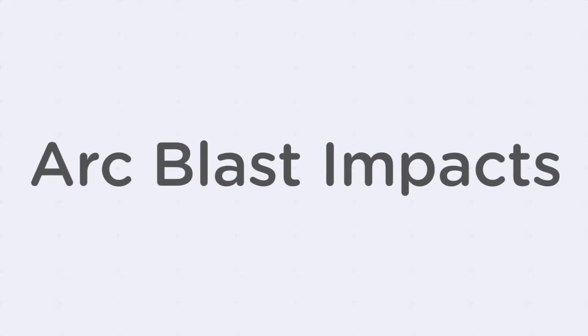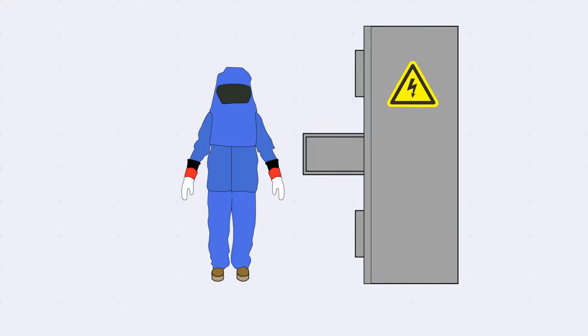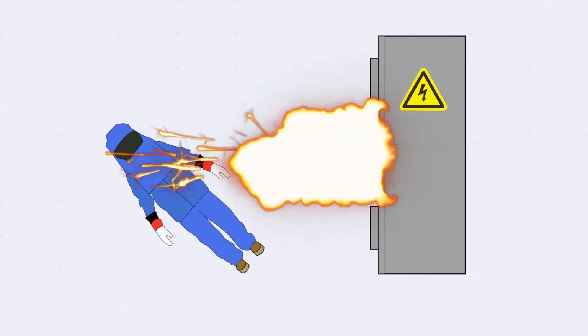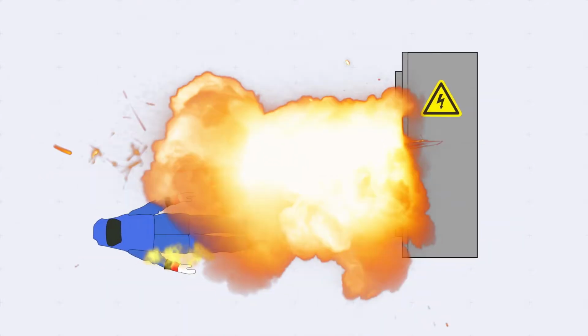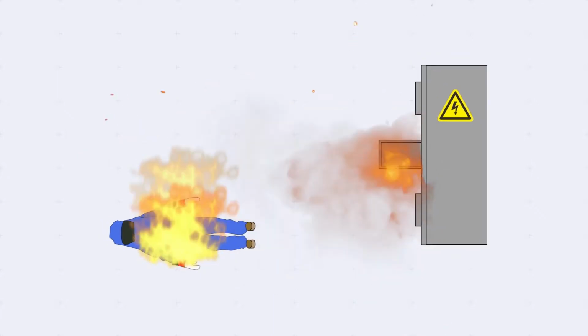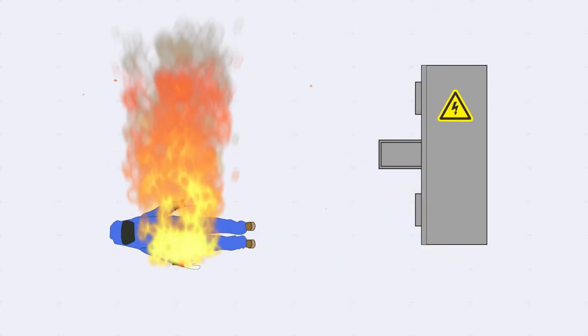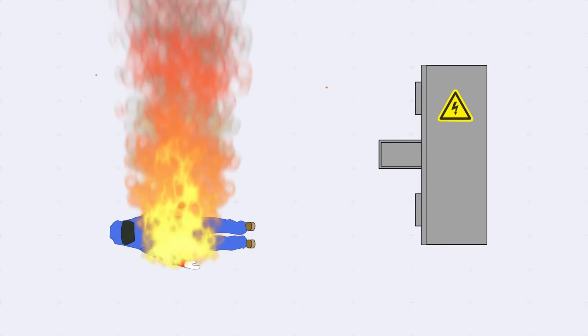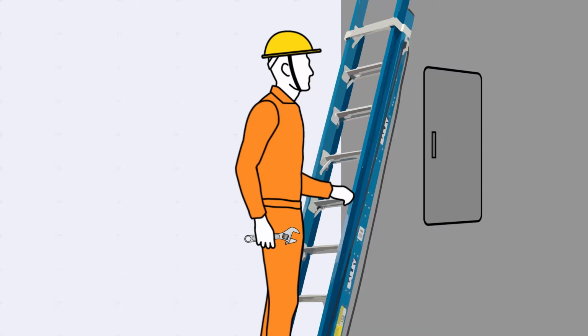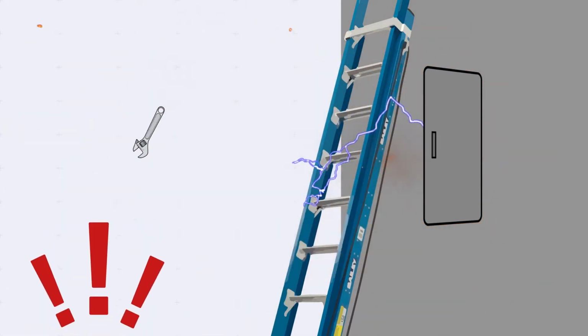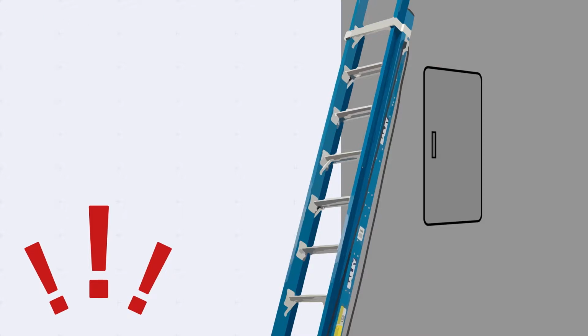When an arc occurs, there is a rapid expansion of air, and this strong air pressure can create an arc blast, which is usually forced to the open side of an enclosure. The noise level from an arc blast can be up to 140 decibels, which can seriously damage your hearing. Materials are often vaporized during an arc blast, causing droplets of molten metal or shrapnel to spray outward. Contact with this shower may cause your clothing to catch fire. Electric shocks and arc blasts can cause affected workers to fall from aerial equipment or drop tools and equipment. Be aware of these added hazards when conducting or assisting with overhead electrical work.